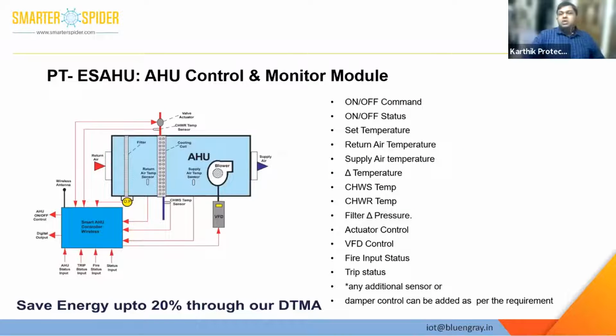So now when it comes to an HVAC, the primary thing is, with our chill water based AHU module, we can give an on-off command, know the on-off status, set the temperature, measure the return air temperature, measure the supply air, measure the delta T of it, then measure the chill water supply, measure chill water return, and then measure the filter pressure. We are measuring these filter pressures because of the clogging.